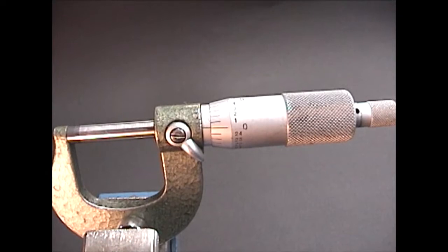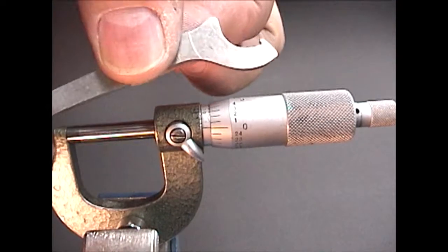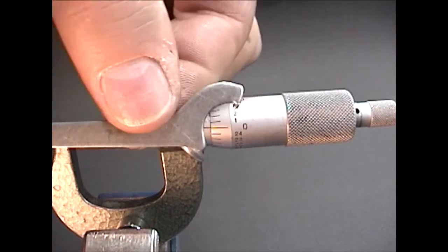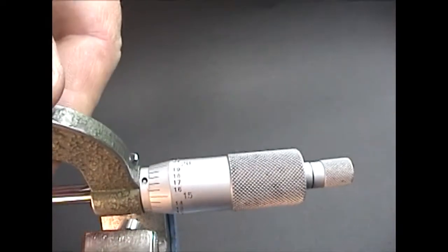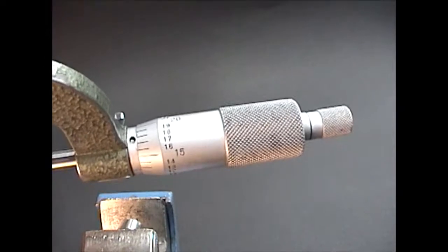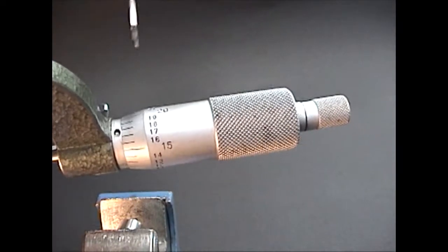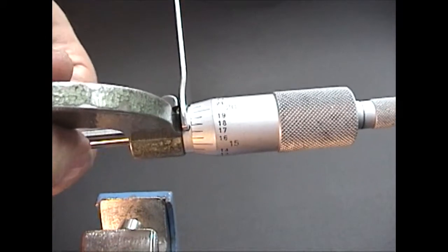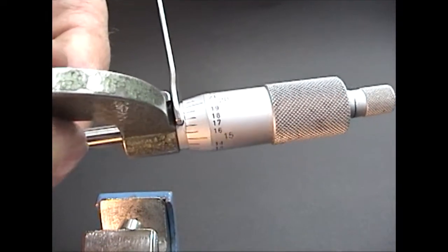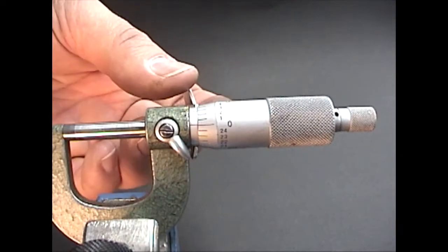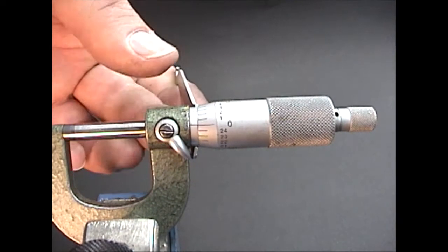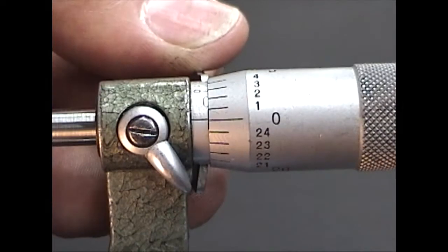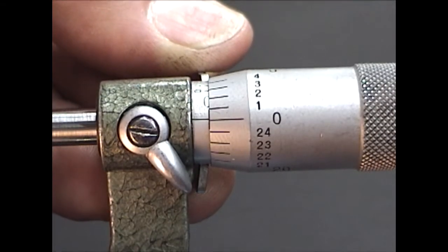On this micrometer, a spanner wrench is needed to turn the barrel. A small hole in the barrel is used with the spanner wrench for calibration. The barrel is rotated to line up the zero marks on the reference line.